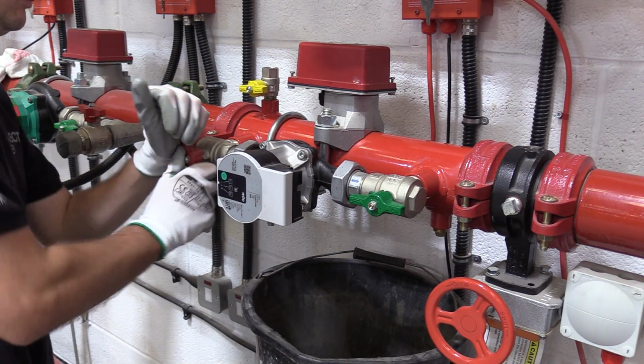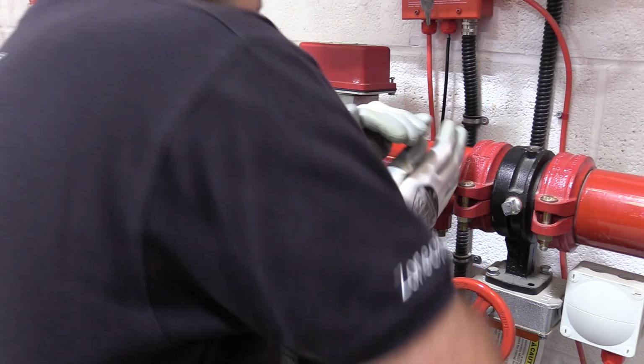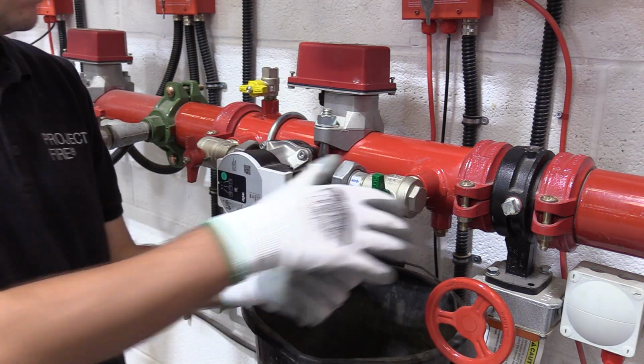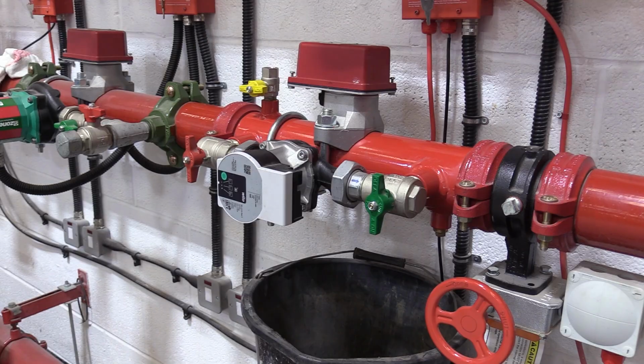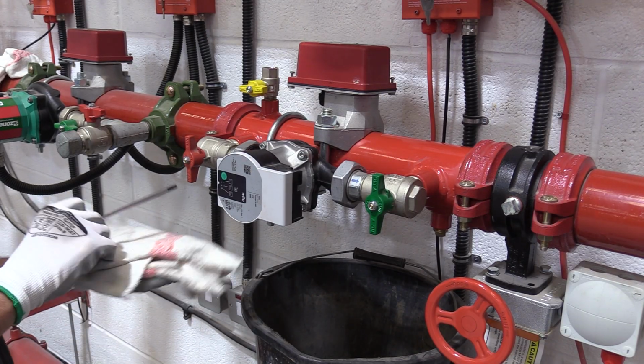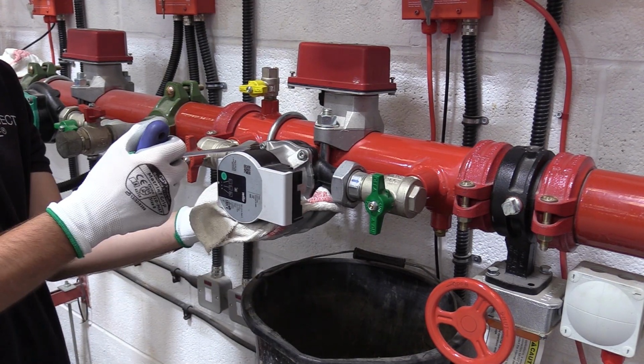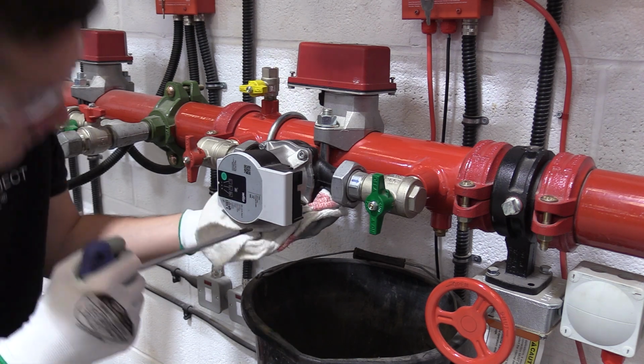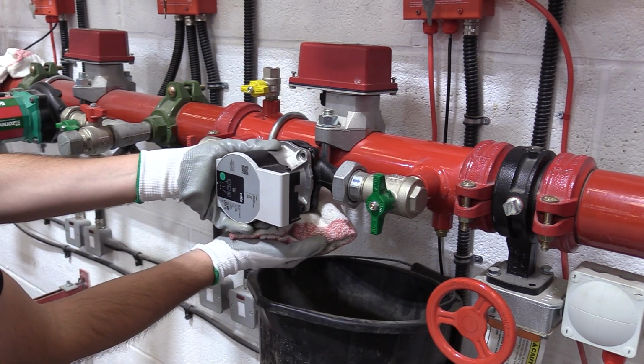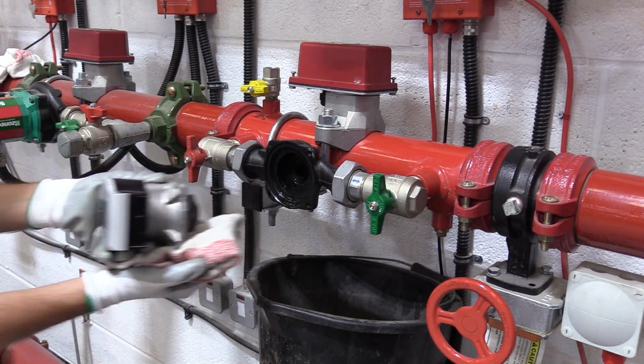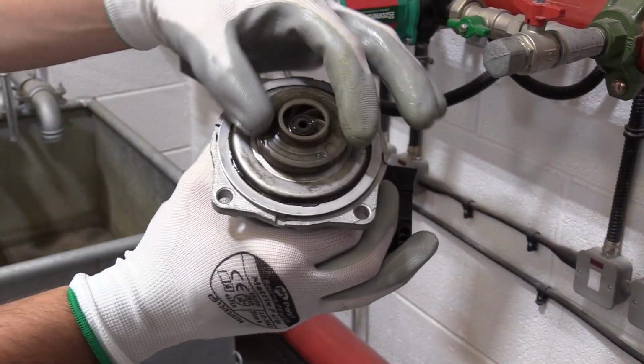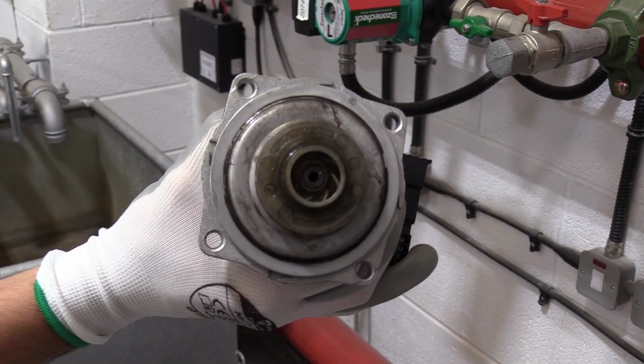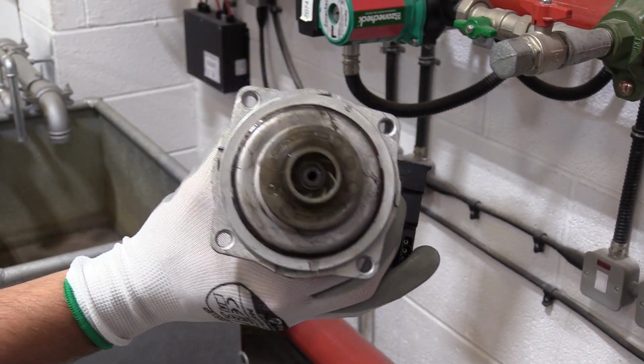With the pump isolated mechanically, i.e. the red and green valves are closed, and isolated electrically, the pump motor or head can be removed to check for seizing and blockages. Remove the 4 Allen bolts around the pump and slide it out. Manually rotate the pump impeller. It should move freely and easily.